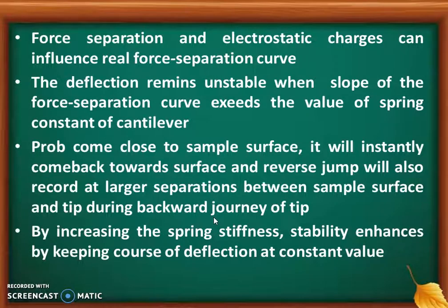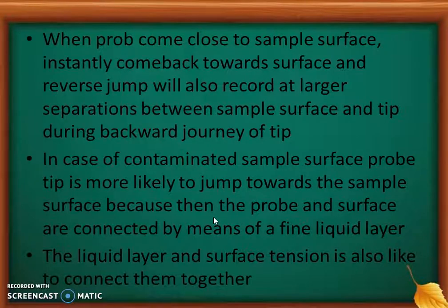The force separation and electrostatic charges can influence the real force separation curve. The deflection remains unstable when the slope of the force separation curve exceeds the value of the spring constant of the cantilever. In this way, when the probe comes close to the sample surface, it will instantly jump towards the surface, and a reverse jump will also be recorded at larger separation between sample surface and tip during the backward journey of the tip.